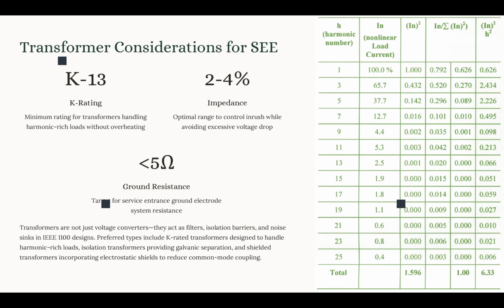One is the K rating of the transformer. You can see the K rating of the transformers in the table in the slides. This is the table of the K rating. The definition is that the K rating basically indicates the transformer's ability to handle the harmonic current without getting overheated. Okay, so the IEEE 1100 asks for a minimum K13 rating. Higher than that is also acceptable. This is a minimum, and when we talk about very extreme harmonic conditions, you might want to move from K13 to K20 or K30.